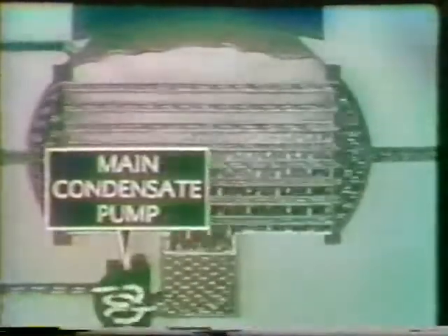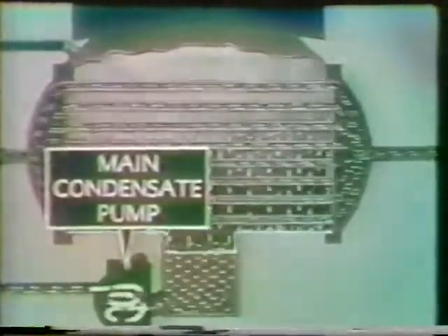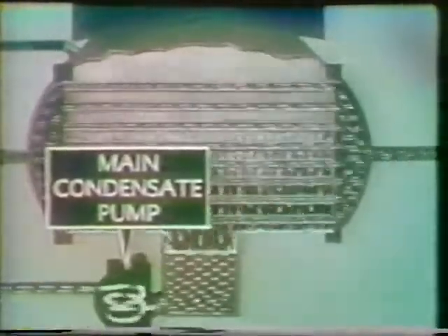As the exhaust steam passes into the condenser, it condenses into drops of water through contact with the cooling tubes. The water, now known as the condensate, collects in the hot well. It is removed from the hot well by the main condensate pump. Air as well as condensate must be pumped out of the main condenser because air cannot be condensed like steam to form a vacuum.